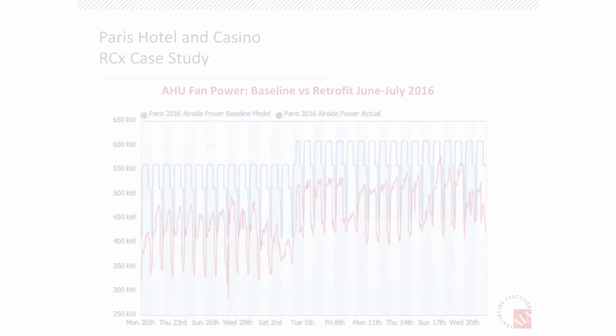The pressure independent valves, the Belimo valves, we put in on 4 of the big air handlers as a trial, basically a pilot, to see how well those work. They're basically trying to match the design GPM through those coils. Those are the big coils, closest to the central plant, so we strategically picked those to try to balance the flow through the rest of the system and make sure we're not over-pumping just because we're flowing twice as much chilled water through a coil as we need. We want to make sure that's balanced so we can get it up to the tower and out to the end of the loops.